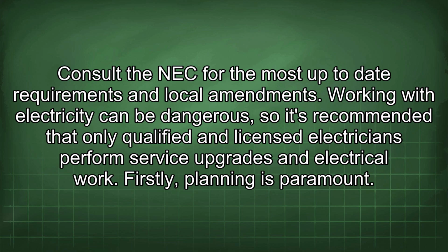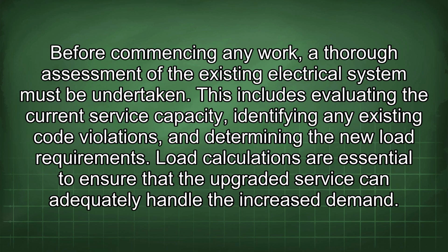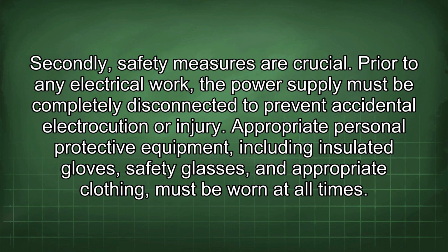Firstly, planning is paramount. Before commencing any work, a thorough assessment of the existing electrical system must be undertaken. This includes evaluating the current service capacity, identifying any existing code violations, and determining the new load requirements. Load calculations are essential to ensure that the upgraded service can adequately handle the increased demand. Secondly, safety measures are crucial. Prior to any electrical work, the power supply must be completely disconnected to prevent accidental electrocution or injury. Appropriate personal protective equipment, including insulated gloves, safety glasses, and appropriate clothing, must be worn at all times.